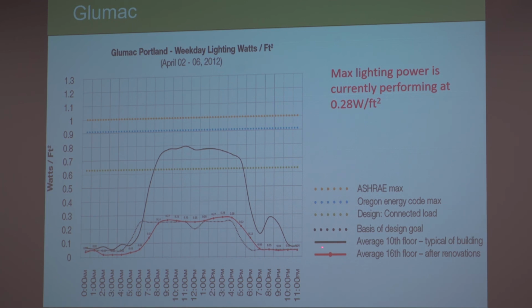This black line, that's the 10th floor. That's not the floor that was renovated. That's just another floor in the building. And you can see throughout the day the lighting power usage. The red line is the floor that was renovated. So they are using about 0.28 watts per square foot of lighting power below their design lighting power because of all the lighting control provisions they put in the building. That helped them easily meet their energy code and actually helped them also get LEED Platinum for the project.